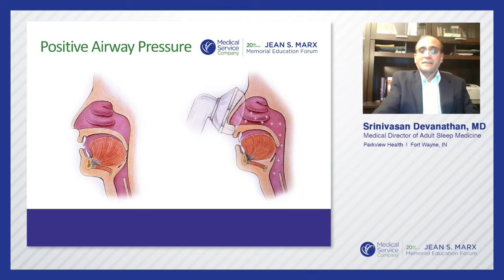We have CPAP, BiPAP, BiPAP ASV, different terminologies used for different scenarios. Central sleep apnea oftentimes has to be treated either with BiPAP and a backup rate or adaptive servo ventilation. The hypoventilatory group oftentimes requires BiPAP or a volume assured pressure support mode. We're going to look at data download information: the number of days used, number of hours used, the current pressure settings, what's actually delivering based on the auto PAP mode or direct pressure, the calculated AHI, which is an average index of how often you hold your breath or breathe shallowly, and the amount of mask leak.